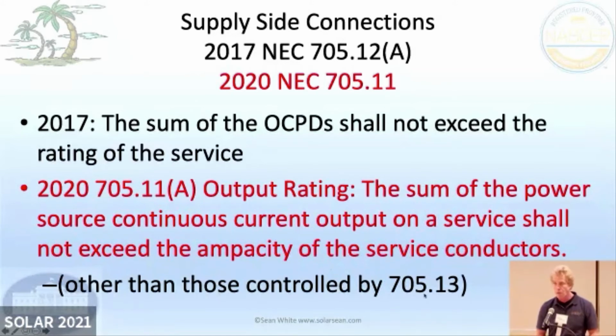This is a new important thing in the NEC that we're not really using yet, but we're going to start seeing it evolve. It might be the coolest thing that's coming out of the 2020 NEC. 705.13 is called power control systems. So that means that we can use electronics to control all these currents. As long as these electronics are making things safe and there's not going to be too much current, then we don't have to follow the load side connection rules and the supply side connection rules, because we have electronics covering these power control systems, PCS.